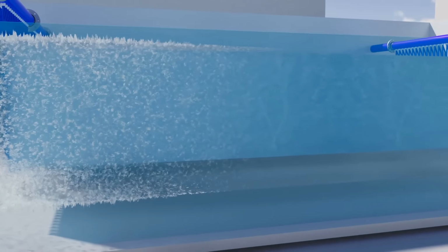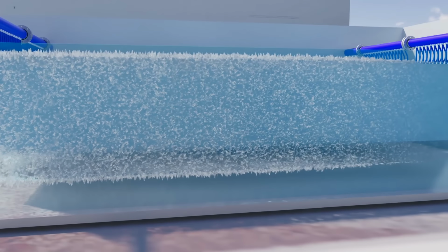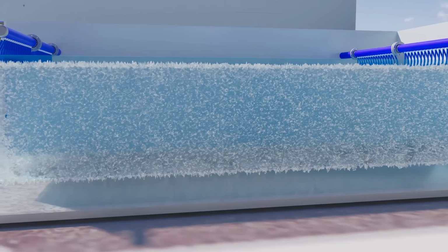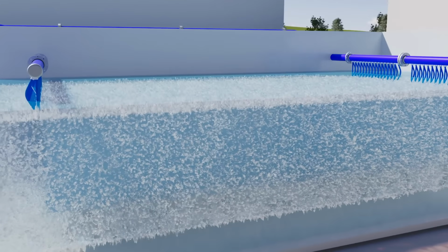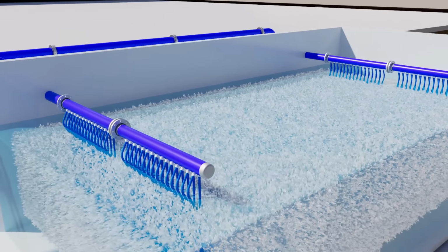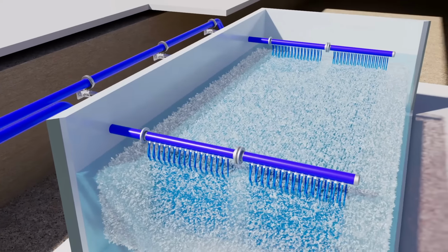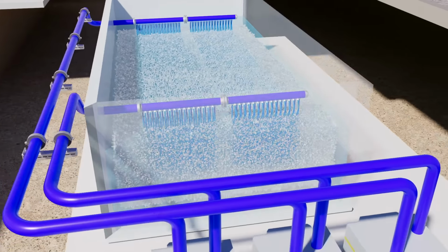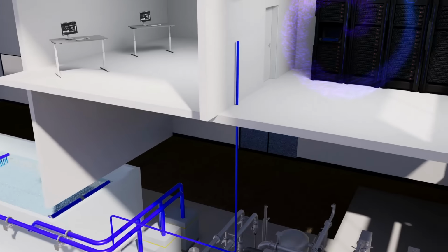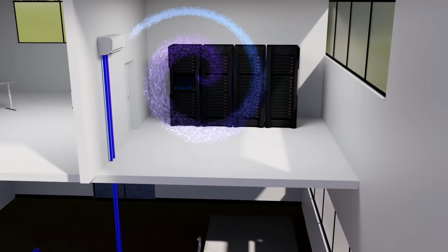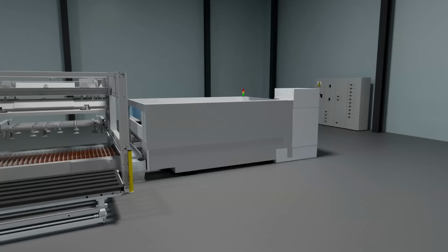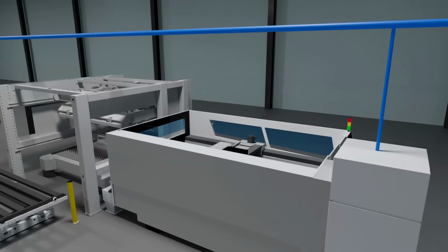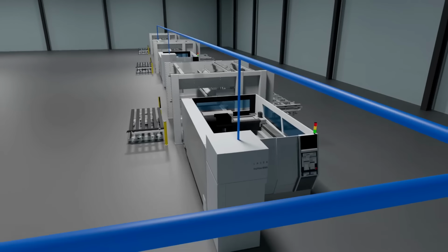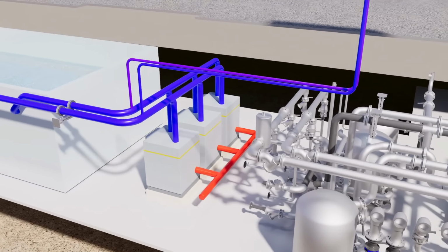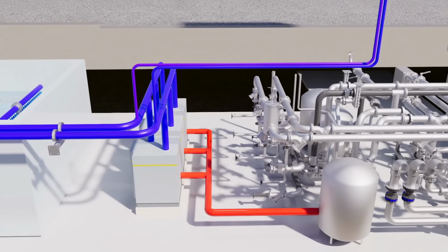Ice particles first form in the absorbers, and eventually, over the course of the winter, a 60 cubic meter block of ice is formed. The ice can expand without causing the storage tank to burst. The cooling energy from this ice storage system is then used to cool a server room. In addition, this system is also used to regulate the temperature of the machines in the production area. The waste heat generated by the heat pumps during cooling is recirculated back into the heating system.